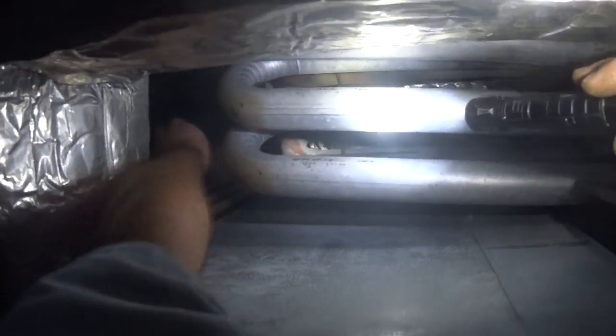that thing is in deplorable condition. The drain pan is slimy, hasn't drained properly in a long time. The heat exchanger is just terrible. Can you hear that? That sucker's getting ready to lose an inducer. I'm probably going to throw junk out of it here in a minute. That's crazy.